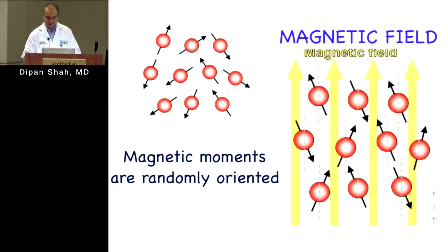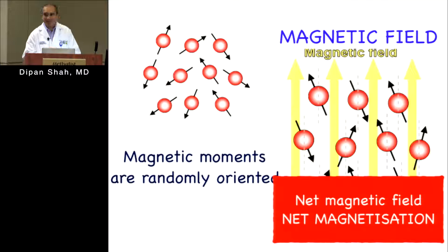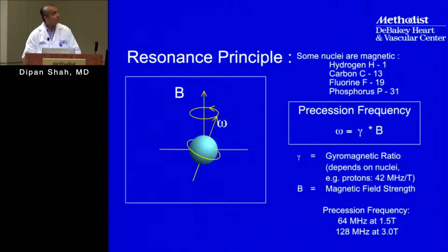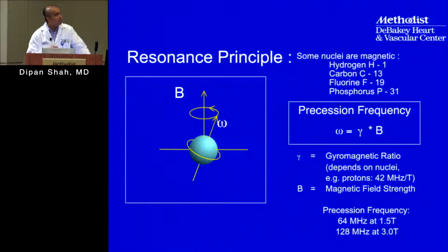Think of the concept of net magnetization. The frequency that these protons spin around at is directly related to the strength of the magnetic field, described by the Larmor equation: precession frequency equals the gyromagnetic ratio times the magnetic field strength. The gyromagnetic ratio depends on each nucleus; for hydrogen it is 42 megahertz per tesla.